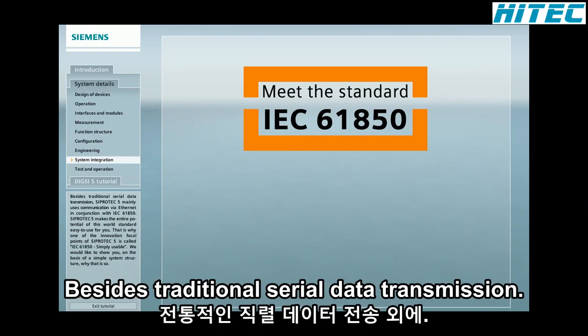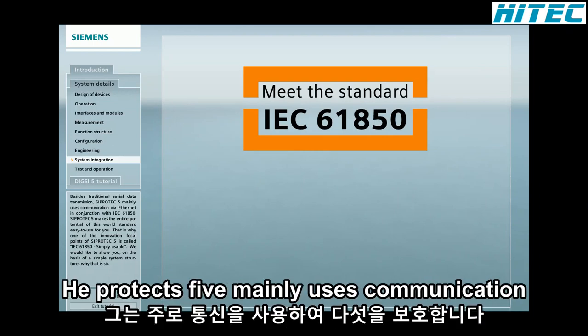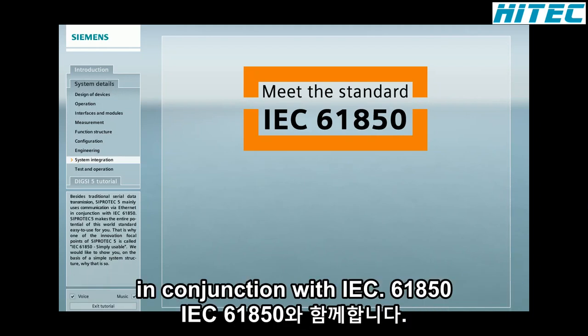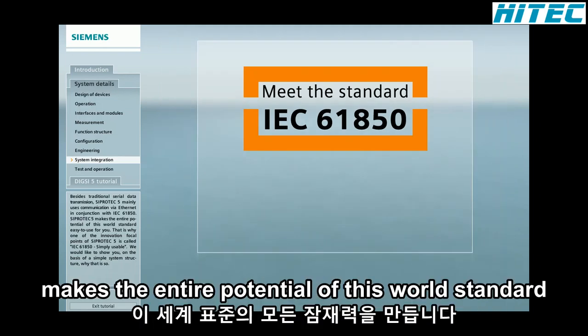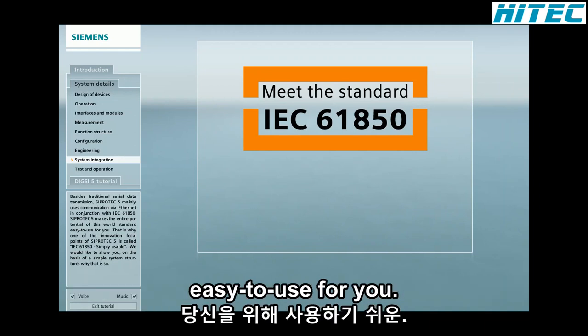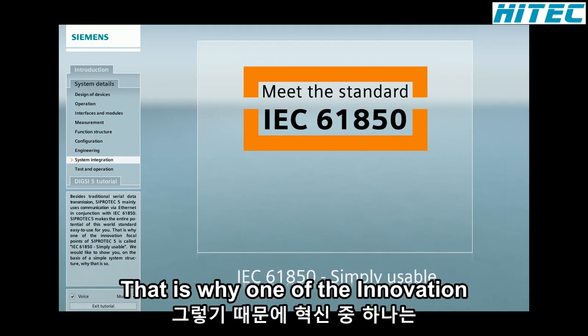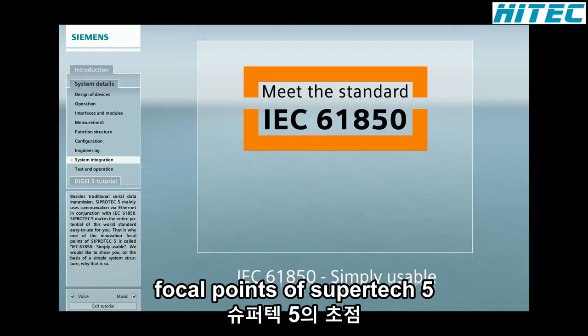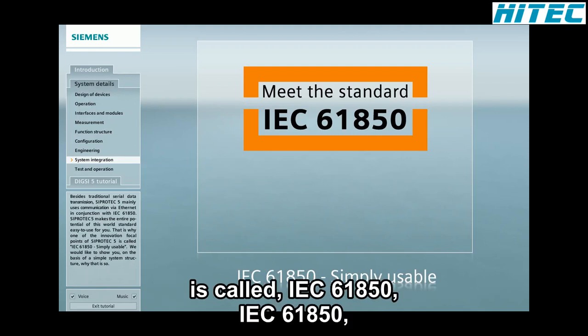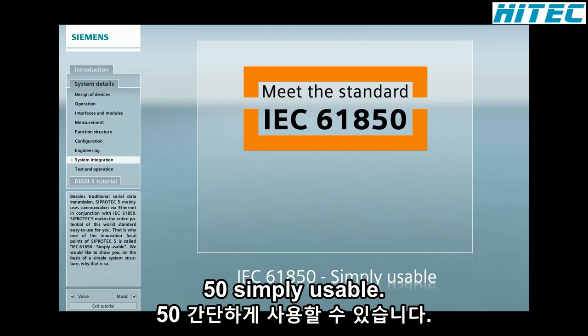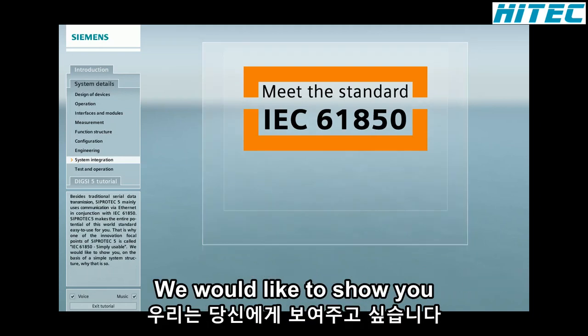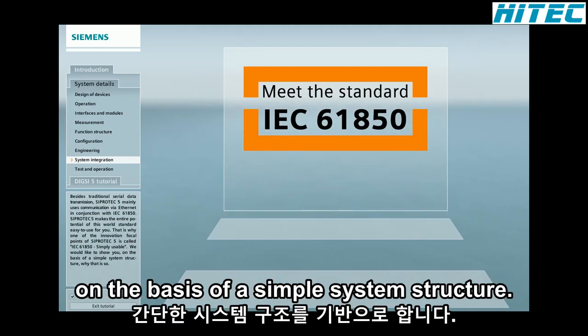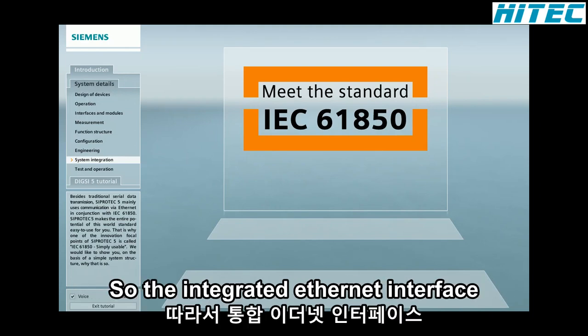Besides traditional serial data transmission, SIPROTEC 5 mainly uses communication via Ethernet in conjunction with IEC 61850. SIPROTEC 5 makes the entire potential of this world standard easy to use for you. That is why one of the innovation focal points of SIPROTEC 5 is called IEC 61850 Simply Usable. We would like to show you, on the basis of a simple system structure, why that is so.